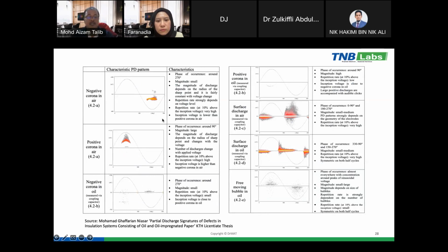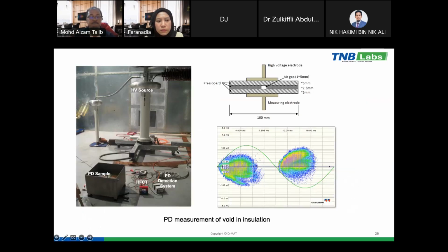And then this is an example of the characteristic PD pattern in oil impregnated paper. So when we have a different fault, we will get a different PD pattern. By analyzing the partial discharge through the PRPD, we are able to detect different faults in the insulation system. So this is an example of PD measurement. This is from the last time our team simulated a PD in the lab. We created a void in the insulation, put it in oil, and then increased the voltage, and finally we were able to detect the void in the insulation. So this is the typical pattern of PD signal when we have a void in the insulation.